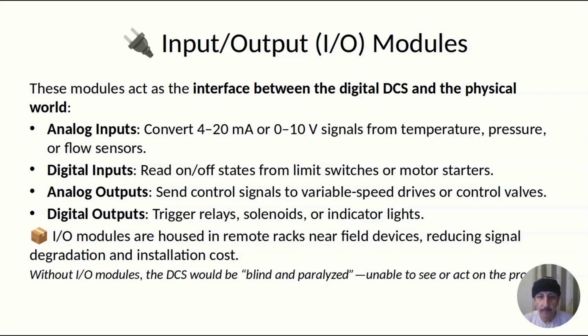On the output side, analog outputs send precise control signals back to the field, like telling a control valve to open 63% or instructing a variable speed drive to run a fan at 1850 RPM. Again, this is usually via a 4 to 20 milliamp or 0 to 10 volt technique. Again, it is important to note that if you are going to try to say 63% or 1850 RPM and that has correlated to a certain current, by using a current loop, you can be assured that your message will be sent across properly no matter what the condition of the wire is.